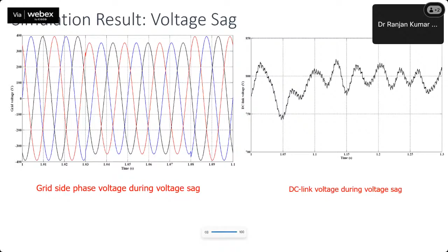Then if you see here, when there is a voltage sag, the modulation index goes high during that period, and also this is the neutral current during the voltage sag.